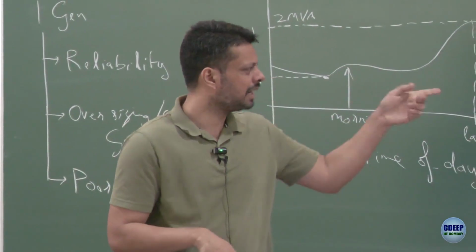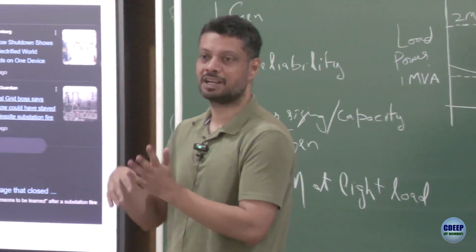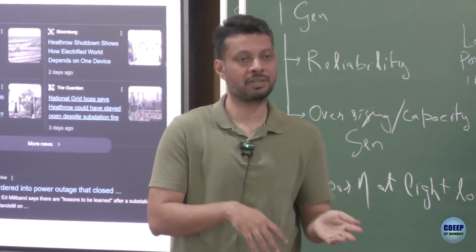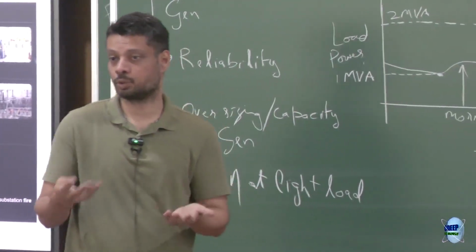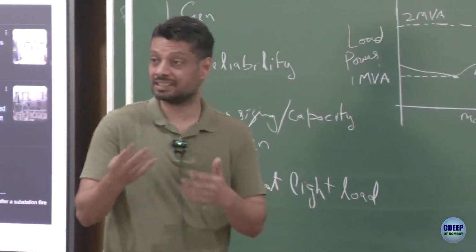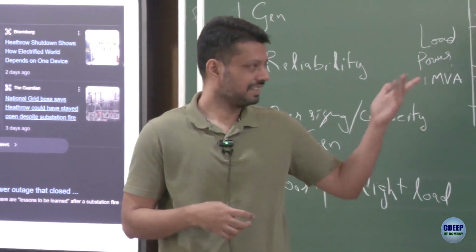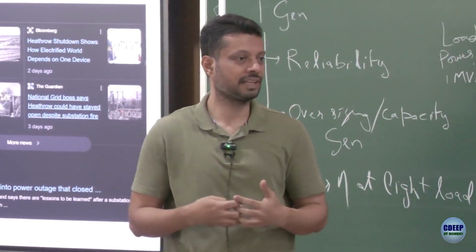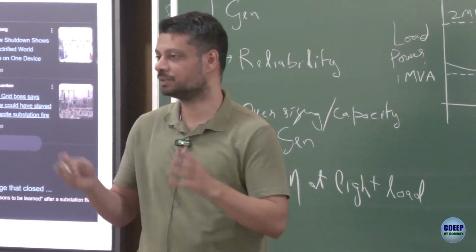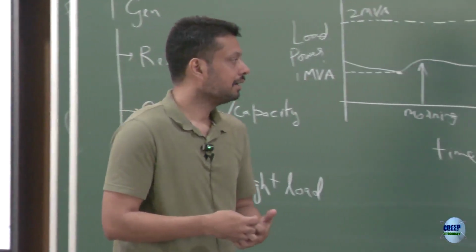But I think one news article said that there were 3 transformers, either 1 or 2 of them were under repair, and then this third one caught fire, and then nothing could be done. It took quite a lot of time to restore the other 2 and get the power back. There is some value, 78 million USD, I don't know if it makes a lot of sense, but there was of course a huge loss because of all the flight cancellations, flight diversions and so on.